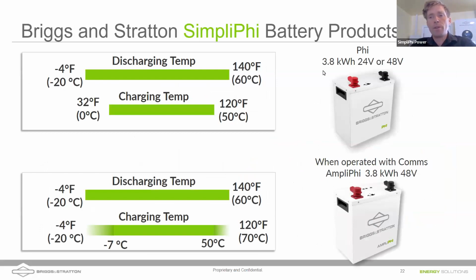Now, our PHI battery is a non-communicating battery. What we mean by that is the internal computer, the battery management system, does not communicate with charging equipment. It's got preset values in there on the BMS to protect and balance the cells, but it cannot tell charging equipment how fast it wants to be charged and discharged, etc. So the charging range for this battery is specified on the screen, and the discharging range is a bit broader.